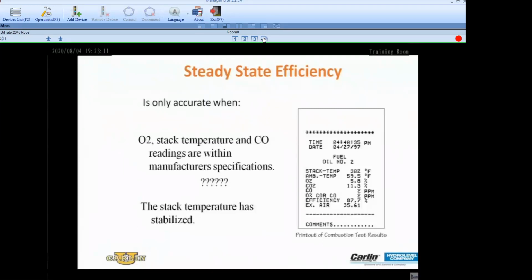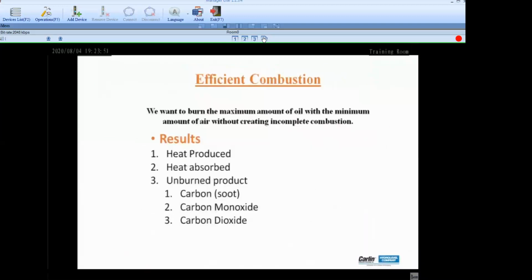The most common misconception that technicians might have when doing a combustion test is a lack of understanding of what the O2 means. They know it means oxygen. And somebody told them that and they said, well, this is good. I've got 4.5%, I've got 5%, 5.5%. And the question is why? How did you end up with 5.5%? Where does that number come from? And most technicians will not be able to answer that question. These are the things that we explore when we get our results.